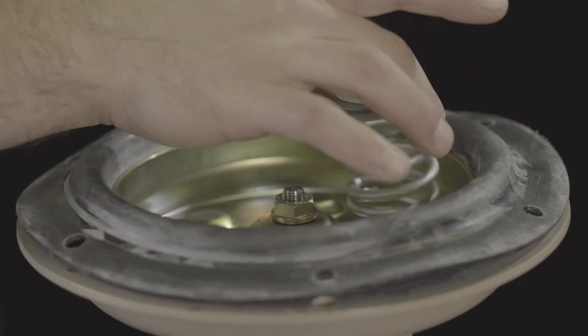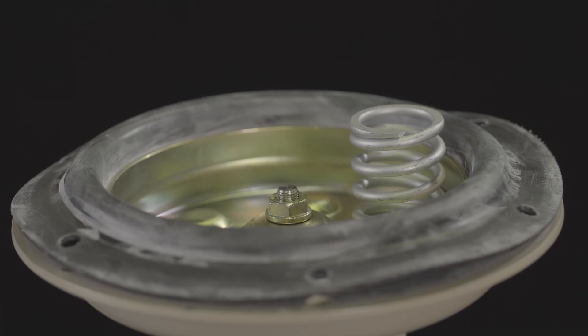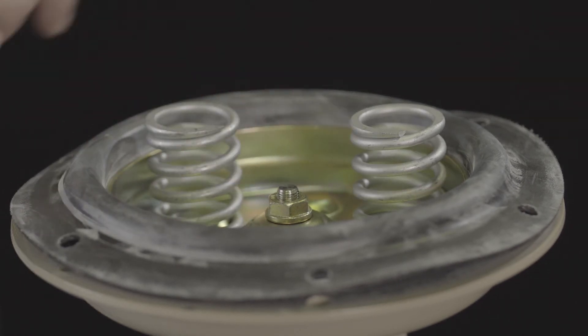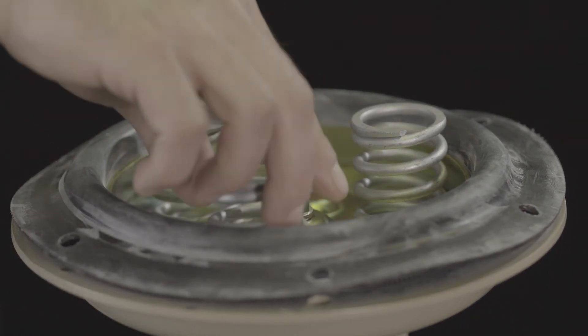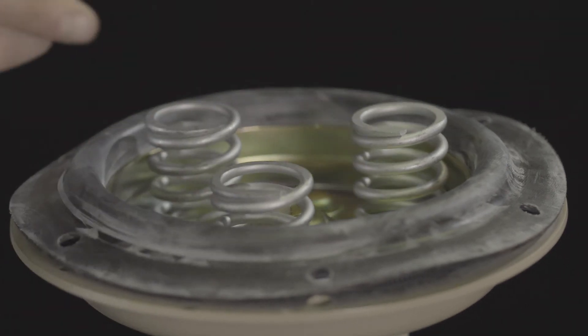Place the springs onto the diaphragm plate, centering them in the intended recesses. The final actuator spring range will determine the appropriate springs to be installed.